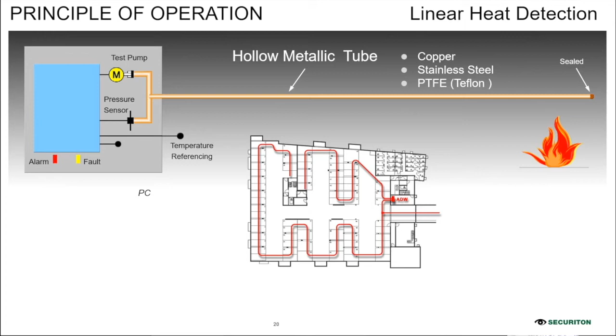Now I can give you the focus on our two models, which is ADW 535 dash 1 and dash 2. ADW 535 dash 1 covers an area of approximately 800 square meters, and ADW 535 dash 2, which is a two-channel model, covers an area of approximately 1600 square meters. The maximum tube length can go up to 115 meters per channel. So single channel means 115 meters. With dual channel it is 115 into 2, which is as per the EN norms. But the system limit per channel is 200 meters. So you have to decide whether you design as per EN, or you can use the system limits as well.